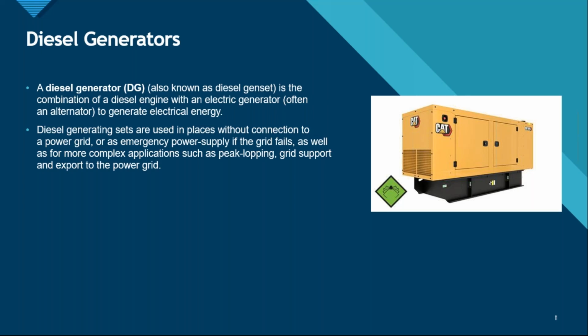Diesel generating sets are used in places without connection to a power grid, or as an emergency power supply if the grid fails, as well as for more complex applications such as peak lopping, grid support, and export to the power grid. The main advantage of diesel generators is that they are portable. So in case there is a construction site and there is no electrical supply, you can always rely on diesel generators to provide electrical supply for the meantime while the electrical connections are getting sorted out.